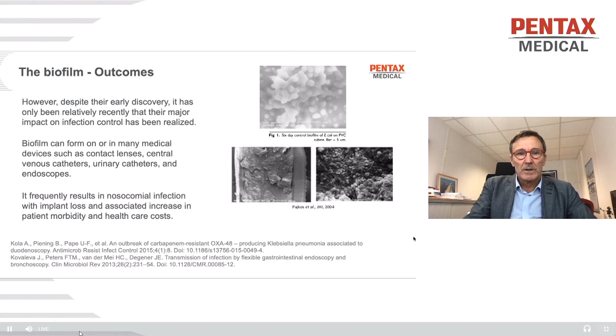So what about reprocessing and cleaning? Current recommendations for endoscope reprocessing include a cleaning step involving immersion of the endoscope in a detergent with brushing of the larger channel and flushing of all channels, followed by high-level disinfection or chemical sterilization.